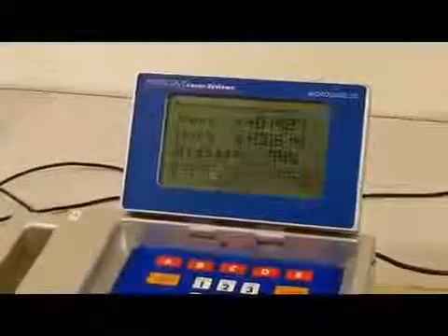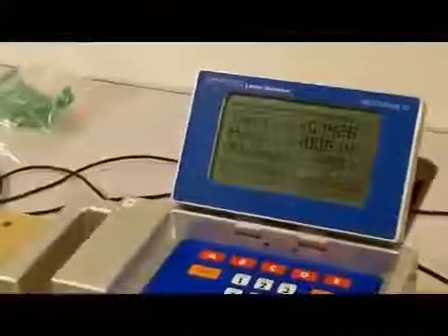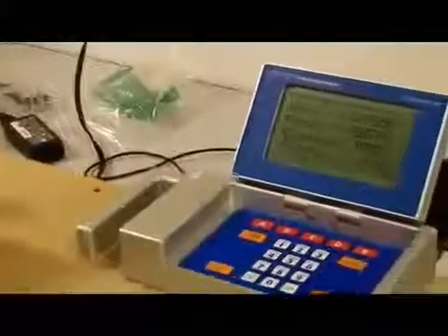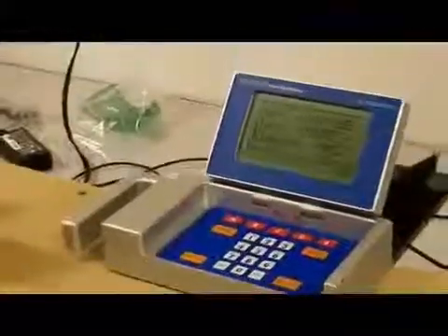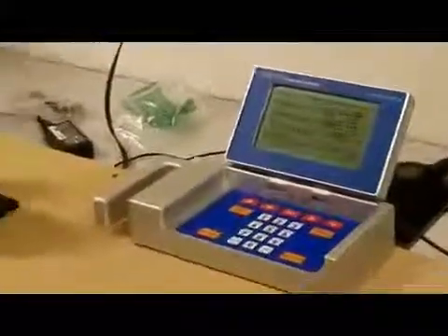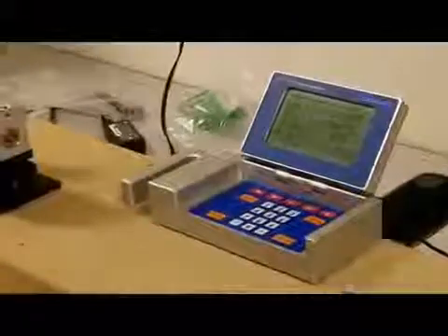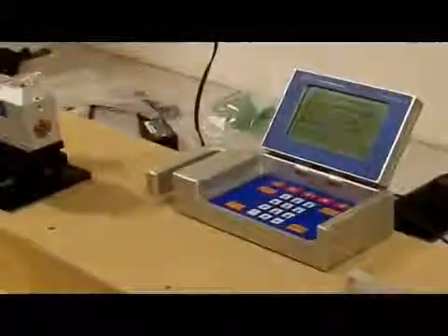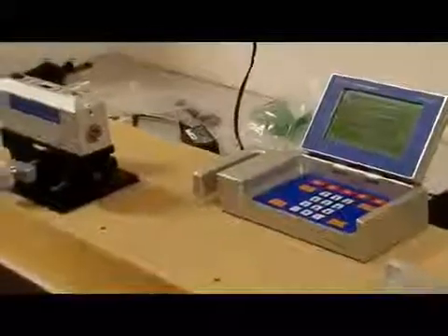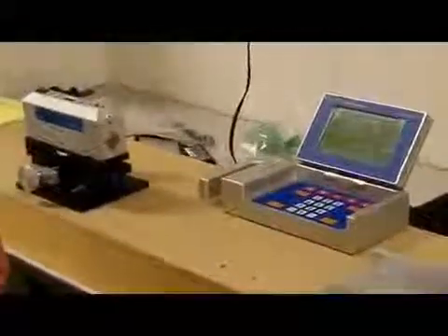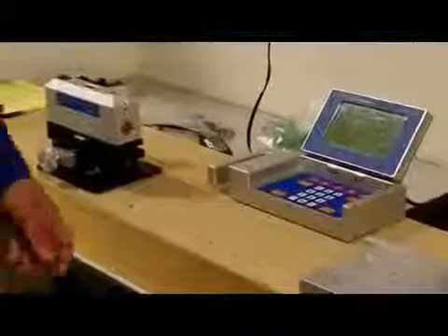Okay, now I have both my vertical and horizontal readings very close to my target values on position number two. I have 0.1428 on vertical and 0.0614 on the horizontal. Now if I move my target from location two back to location one, I should be very close to these readings.